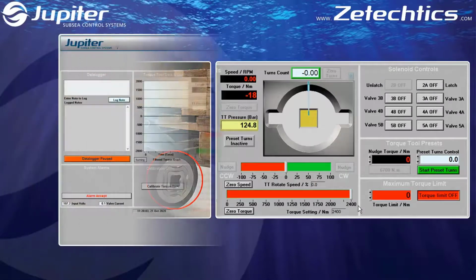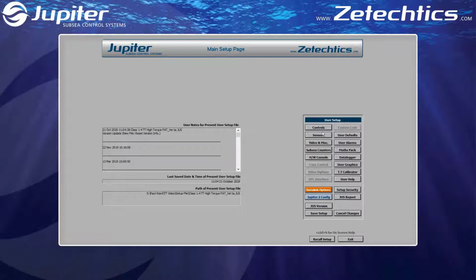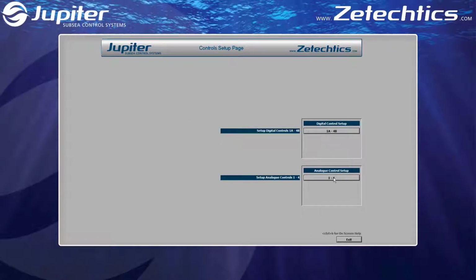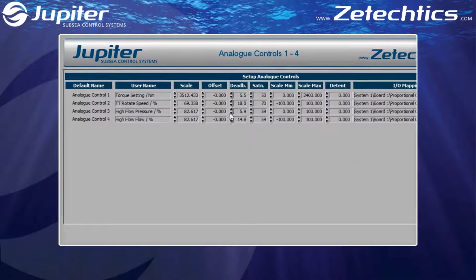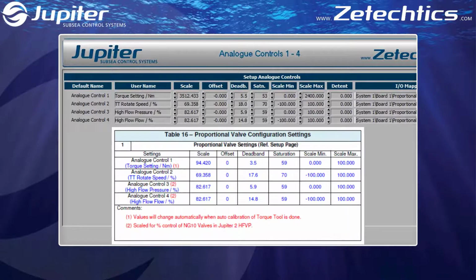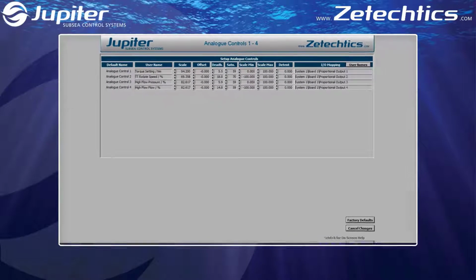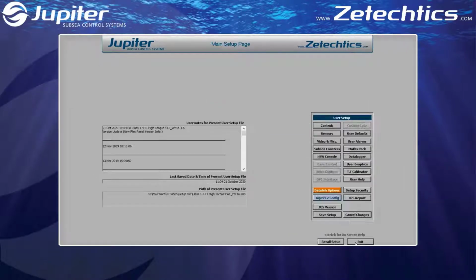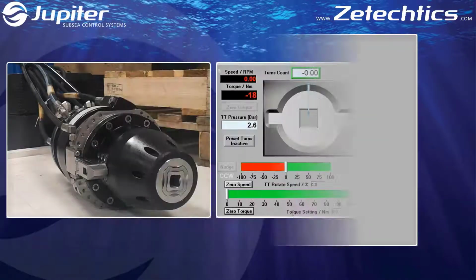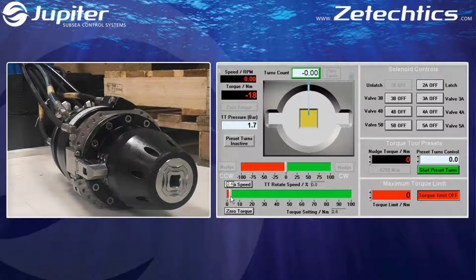achieve full torque. Enter setup pages, controls, and analog control setup to adjust the valve scaling. The valve scale values in the FAT document will allow the full range of operation of the valve. Enter the values, remembering that this will potentially allow over 200 bar depending on the HPU output. Return to the operating page to test the new control range.